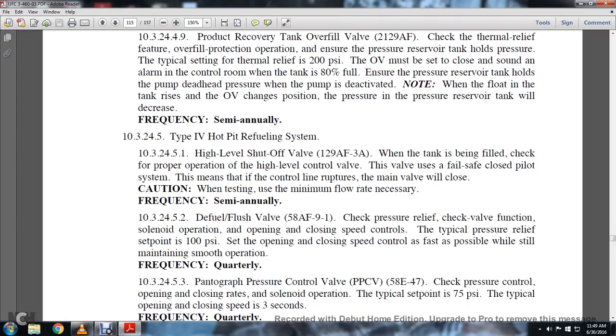Now the Type 4 hot pit refueling system. The high-level shutoff valve: check for proper operation when the tank is being filled, the high-level control valve. The valve is usually a fail-safe closed pilot system. This means if the control line ruptures, the main valve will close. Use caution when testing the minimum flow rate necessary. Frequency is semi-annually. The defuel flush valve: check the pressure relief, check valve function, solenoid operation, and opening and closing speed control.